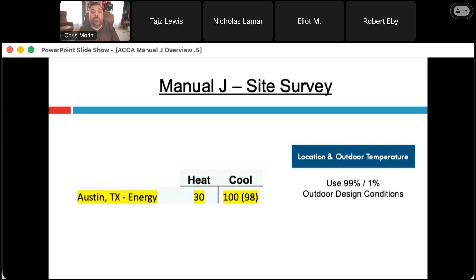So when you design to 100 degrees, it's actually slightly higher than the 99% design temperature. But that's what you should be designing to when it comes to cooling for your building code. Now, if you deviate from that, it's obviously going to oversize a system if you size to a temperature larger. You definitely don't want to deviate from the indoor design conditions whatsoever. So in the International Energy Conservation Code and your building code, you actually have to size to 75 degrees for inside design temp and cooling, and 70 degrees plus or minus 2 for heating. Most people just actually size to 70. They don't go up or down on that indoor design condition.